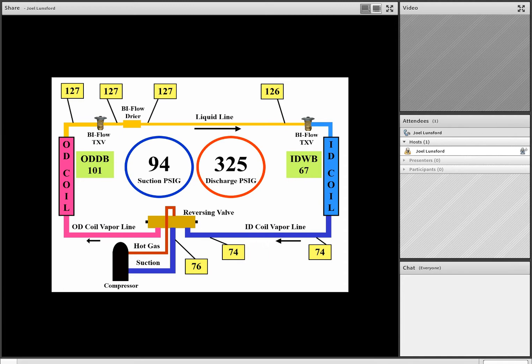But let's go ahead and take a look a little bit deeper and look at our superheat and subcooling as well. So at 94 pounds of suction pressure, we see that we have a 56-degree pressure temperature conversion on the suction side. So at 56 degrees, we notice that the indoor coil has got about an 18 to 20 degree superheat. Now remember, team, we need about 10 to 15. So the superheat is elevated on the indoor coil. That means that coil is starved to slightly starved. Let's keep working.